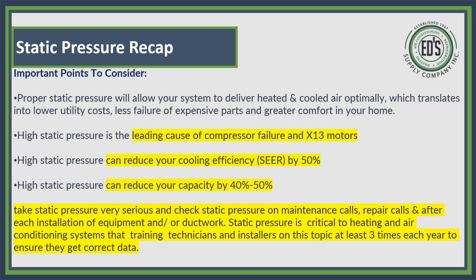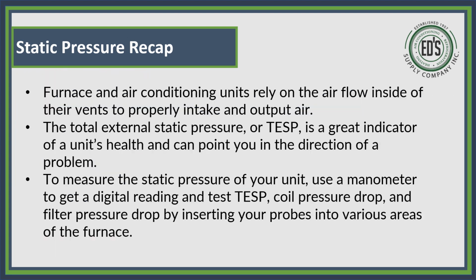So then we look at it's the leading cause for compressor failure in X13 motors. It also will reduce your cooling efficiency SEER rating by 50%. Right? Because we're looking at half the CFMs it's supposed to be doing, and it can cause your capacity to be lost by 40 to 50%. Take static pressure very seriously and check static pressure on maintenance calls, on repair calls, and after each installation of equipment and/or ductwork. Static pressure is critical to heating and air conditioning systems. Training technicians and installers on this topic at least 3 times a year is to ensure they get the correct data. It's so very important and vital for companies that want to be successful.